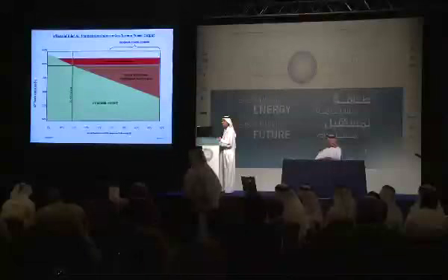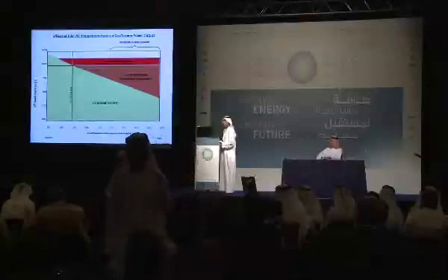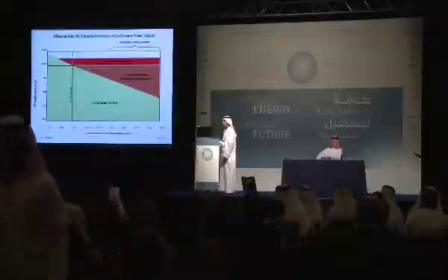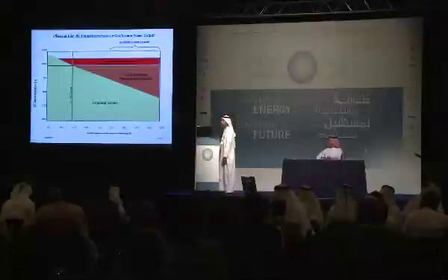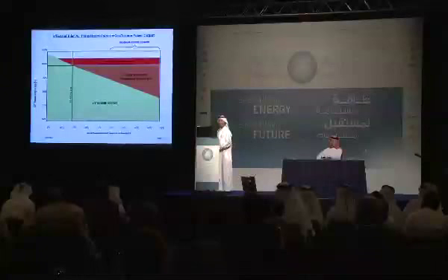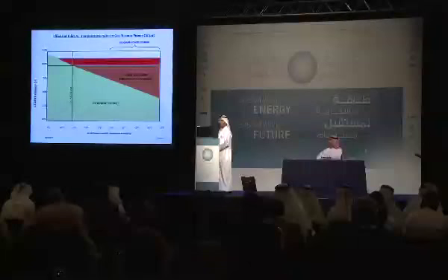Normally, for each 1 degree temperature increase, for the F class, the big units, around 1.8 megawatt reduction, for the E class around 0.9 for each degree ambient increase. So in this region, around 20% of the capacity that we paid for, we cannot utilize. This is the output of the gas turbine.